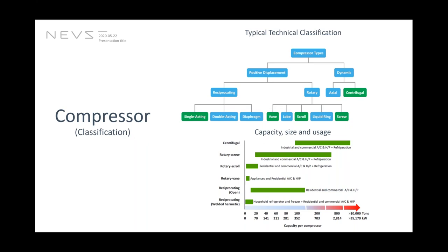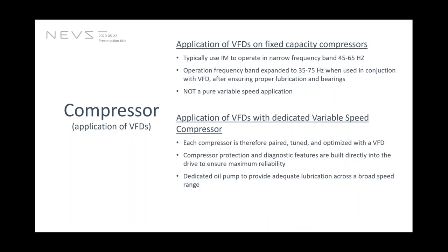What types of compressor are available, capacity, size, and those things. In this slide, you can see the compressor types, a typical technical classification. I don't want to go into the detail of it. And the sizes, what is available, different types, that's fine. But what I'm particularly interested in is the use of VFD in compressors. I can classify the application of VFD in compressors as VFD on a fixed capacity compressor and VFD on a variable speed compressor.